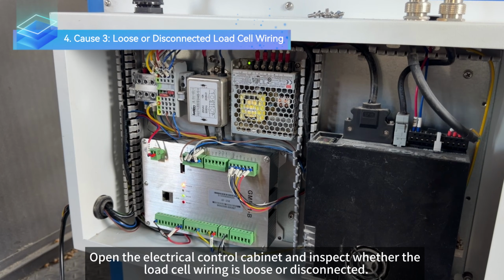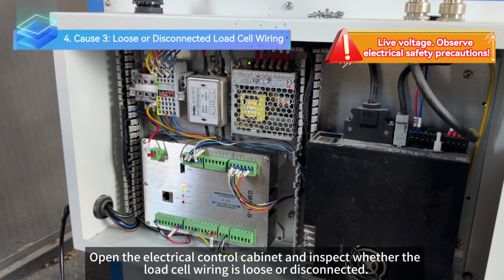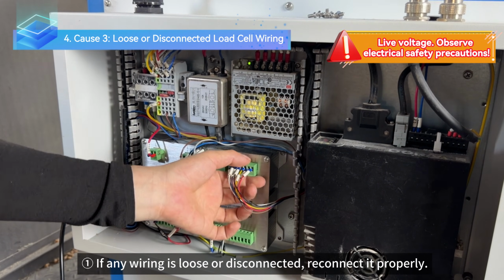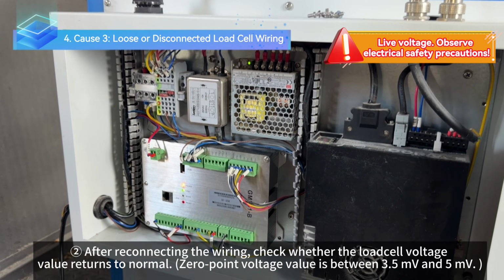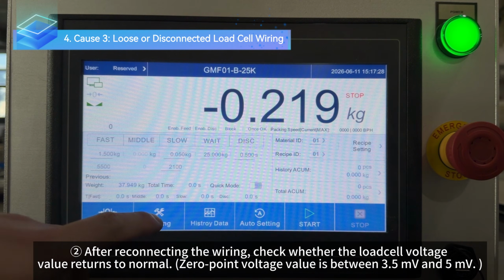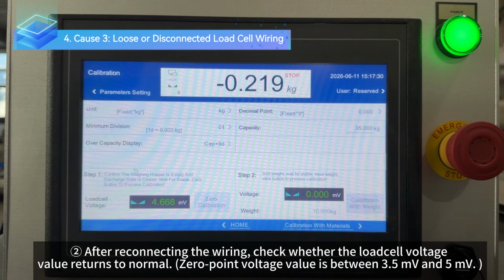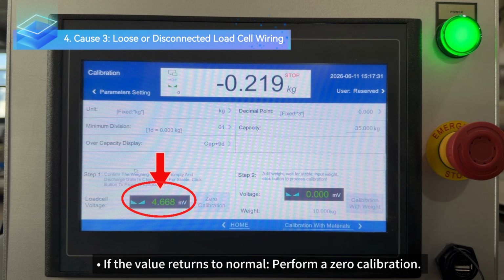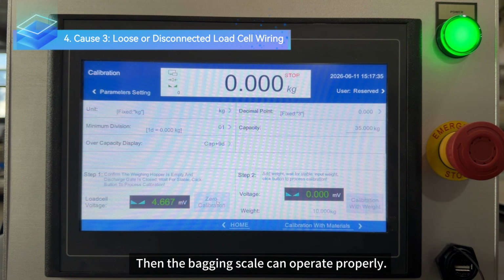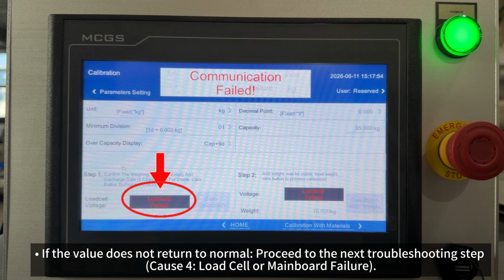Open the electrical control cabinet and inspect whether the load cell wiring is loose or disconnected. If any wiring is loose or disconnected, reconnect it properly. After reconnecting the wiring, check whether the load cell voltage value returns to normal. If the value returns to normal, perform a zero calibration. Then the bagging scale can operate properly. If the value does not return to normal, proceed to the next troubleshooting step.